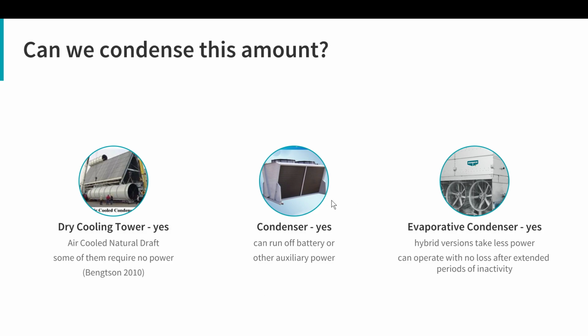One sort of efficient option could be using a condenser, but these run off of electrical power, so we would have to have another source of power, which kind of goes along with the same problem that they had with the reactor coolant pumps. So an evaporative condenser was also a good option. Takes a lot less power than a condenser, and even though it has some of the internals of a condenser, it also has cross flow in there like a cooling tower. And so one of the notable things about this type of evaporative condenser is that it can operate with no real loss after just sitting there for a long time, which is what this would have to do, of course. We're not going to be using this all the time. This would be used only for testing to make sure it's working, and in the case of like worst case scenario.